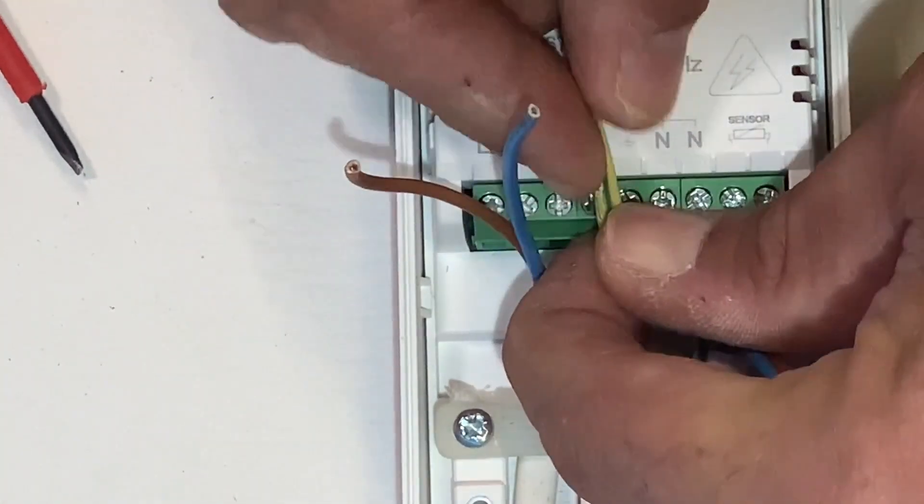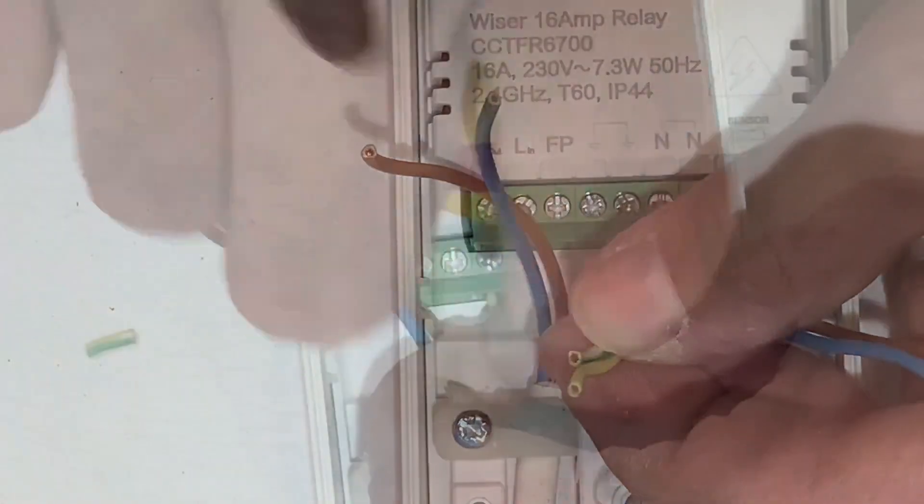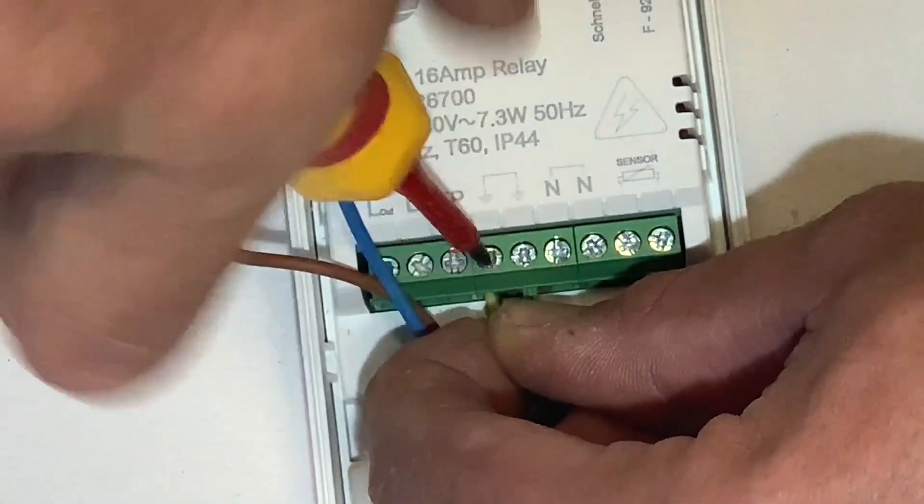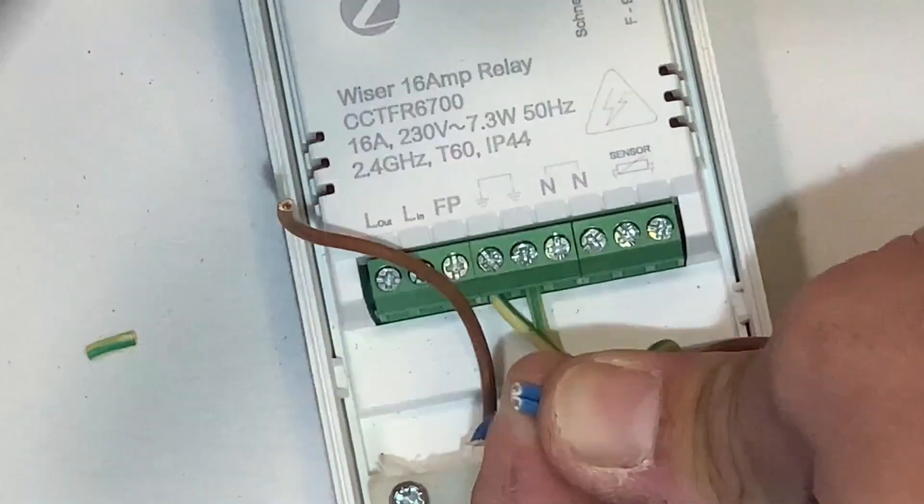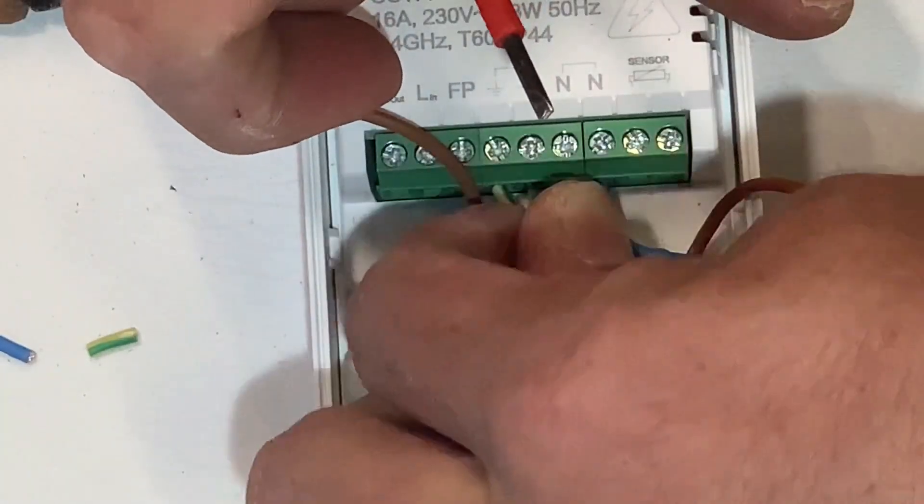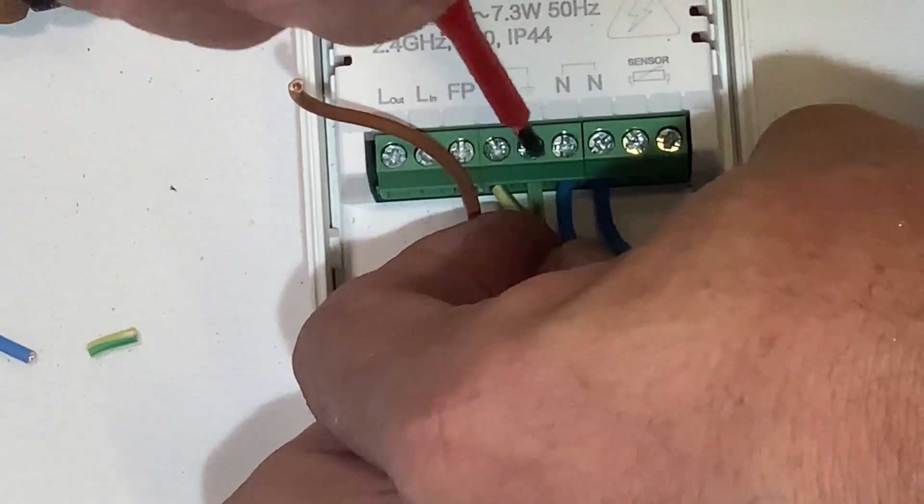First I'll focus on the wires that connect together. The two earth wires here go into the earth terminals and it doesn't matter which way around these go. Next up, the two neutrals, and again the terminals are linked so it doesn't matter which way around they go.